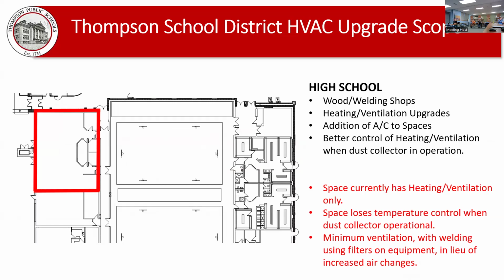Right now, when the rooms are at status quo, they're able to maintain temperature comfortably. However, once they start doing operations and the dust collector goes into operation, it basically sucks the environment out of the space. So if it's warm in there during the winter, it becomes cold. If it's cooler during the summer, it becomes hotter. So updating the units in both rooms, as well as the exhaust, will provide better control of not only heating and ventilation, but also the addition of air conditioning to the space.